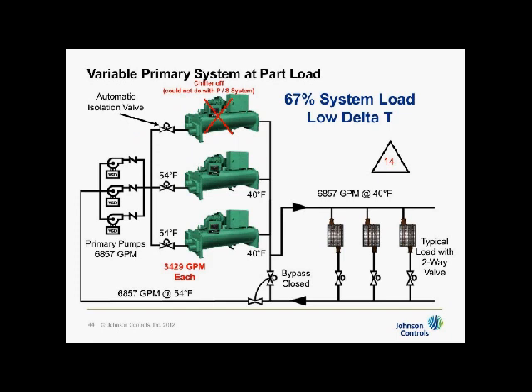It didn't click. Oh, sorry. Yes, it did. Okay, now I've got low delta T, 67% load, but now instead of 6,000 GPM here, I have 6857, just like I did before with the primary secondary. So 6857 travels through the whole system, everywhere, and it reduces my delta T. I have 54, not 56 entering now. But I can shut this chiller off, and I can isolate it. And I can overpump these 2 chillers that are designed at 3,000 to 3429 and take care of having to run more chillers than I need.